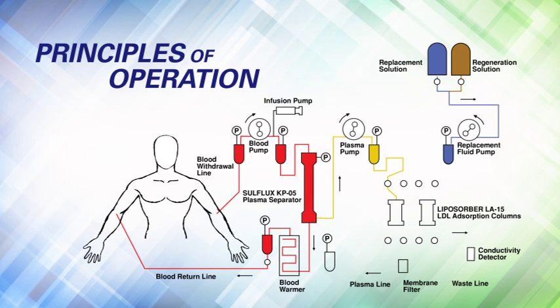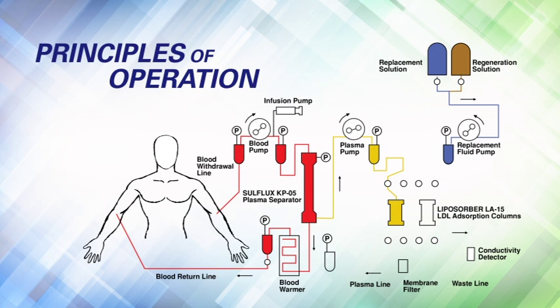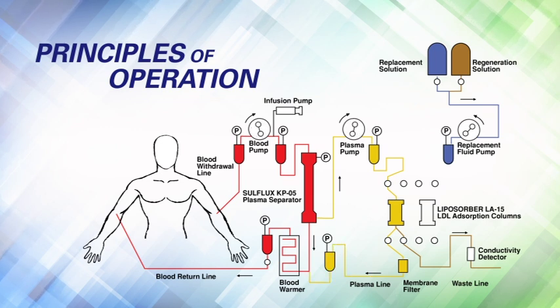The plasma enters the top inlet of one of the two LDL adsorption columns. As the plasma passes through the column, the ApoB-containing lipoproteins — LDL, VLDL, and Lp(a) — are selectively adsorbed in the column. The LDL-depleted plasma exits the adsorption column, flows through the membrane filter, and is recombined with blood cells exiting the separator bottom outlet and returned to the patient via venous access.